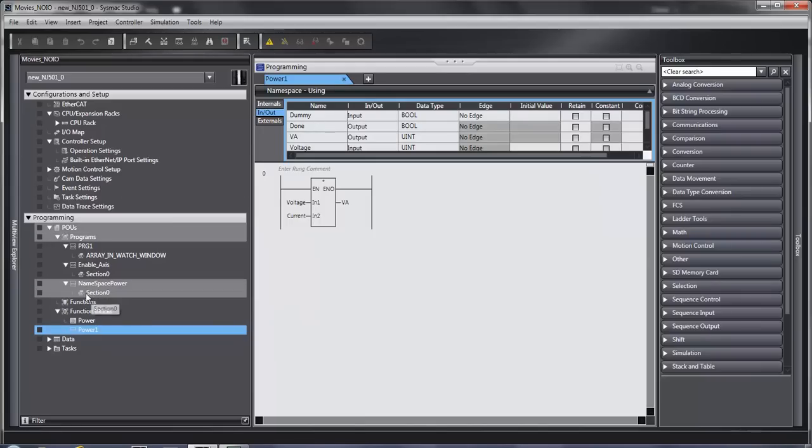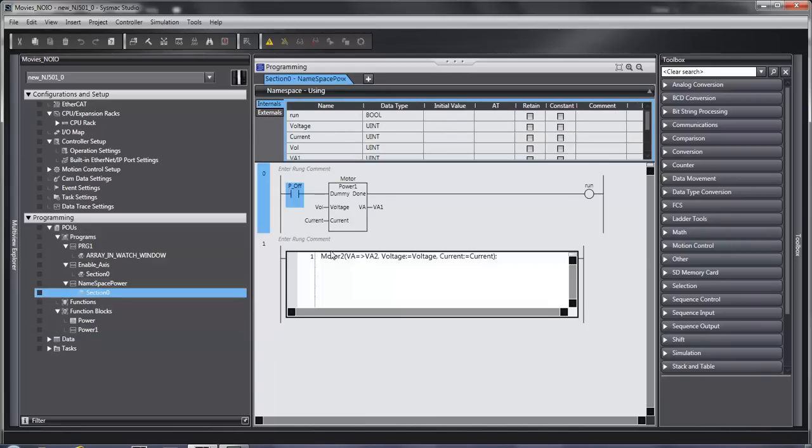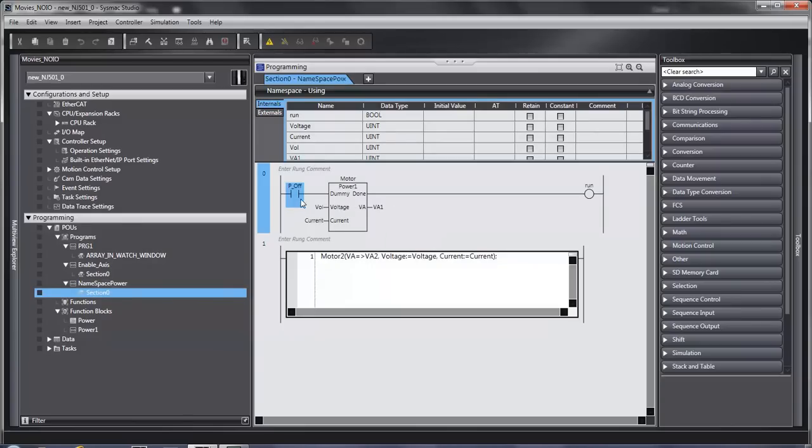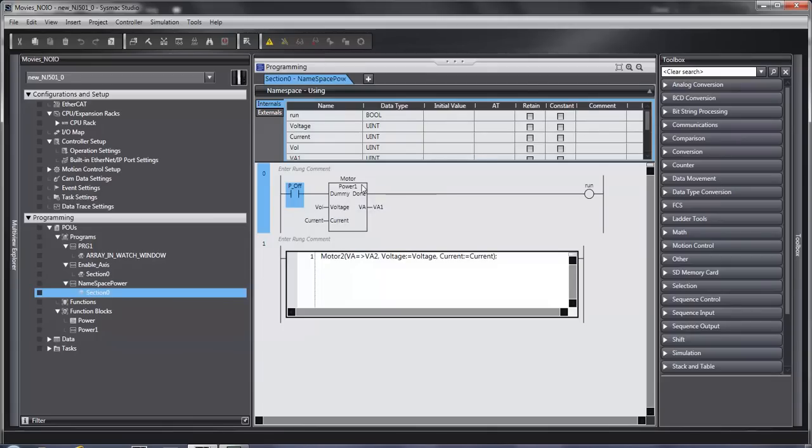So the next piece that you need to know is because they are not used, they don't actually enable a block like all the built-in function blocks. This input in the top left corner normally enables the function block. If you want it to enable what's happening in the function block, you would have to write code to do that.